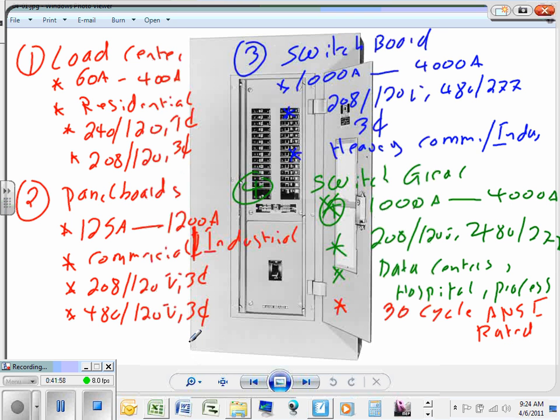Let me just say a load center. Load center, very few things, guys. When you think load center, always think up to 60 amps all the way to 400 amps, if even, up to 400 amps. That's a limitation, Eric, there's a limitation on the amps. Big deal, limitation on the amps. Number two, think residential, always. Think residential, always, when you think load centers.